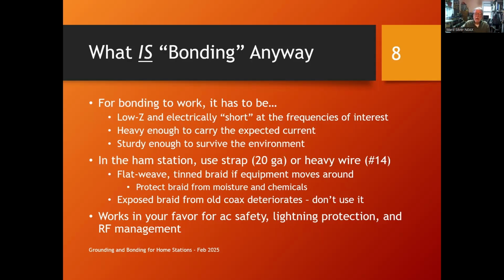This conductor has to be heavy enough to carry the expected current. So if you're just grounding within the station, you might not need a very heavy wire to get the job done. If you're talking about grounding for AC safety, the rule, according to the building codes, is that the conductor has to be capable of carrying all of the current supplied by the branch circuit. So if you have a 20 amp breaker on that branch circuit, your ground conductor to everything powered by that circuit has to be capable of carrying enough current to open that breaker. That's the whole point of that conductor: to cause the protective devices to trip and remove power from the circuit. So it has to be heavy enough to carry that current.